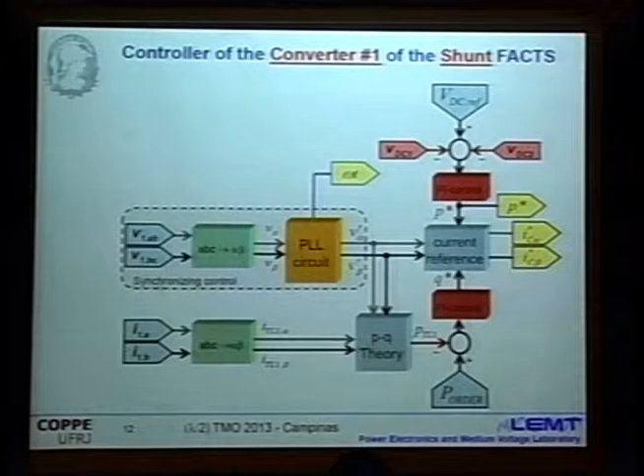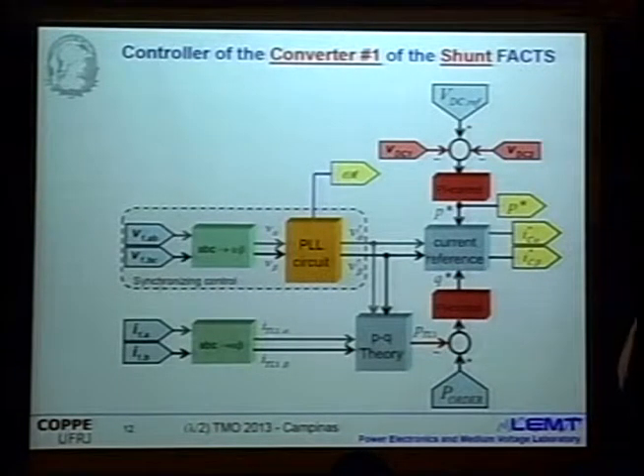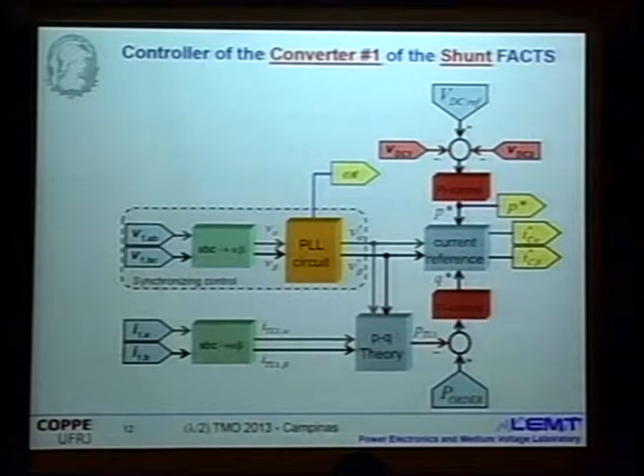I have already tracked the fundamental component for positive sequence in the voltage where the tap shunt is connected, and with it I have the phase angle for this positive sequence voltage. With that, by calculating the power of the line with a little more than half a wavelength, I compare it with its reference, as we saw.